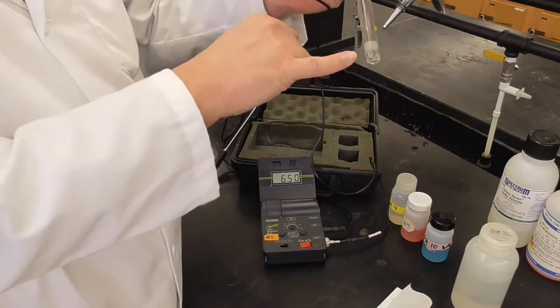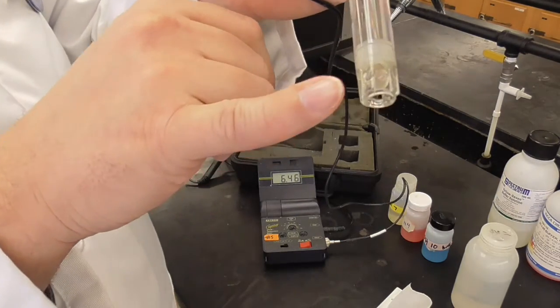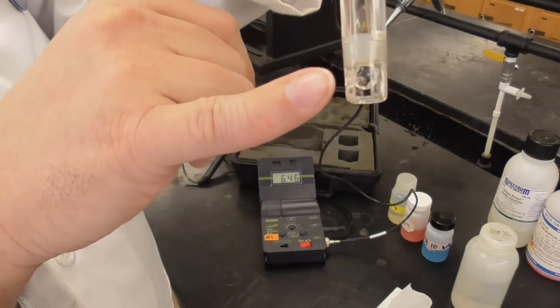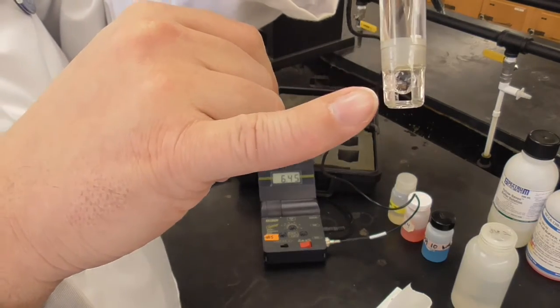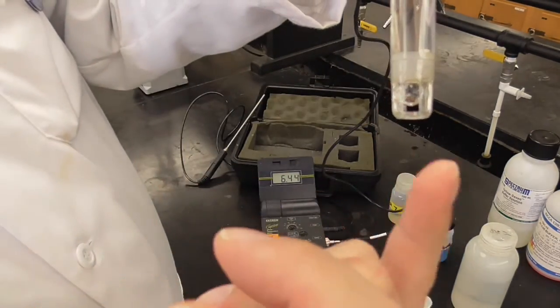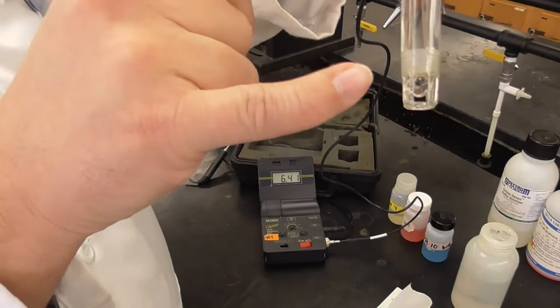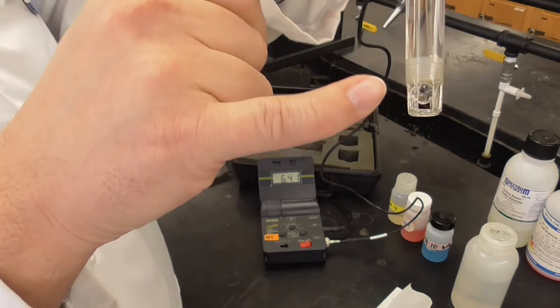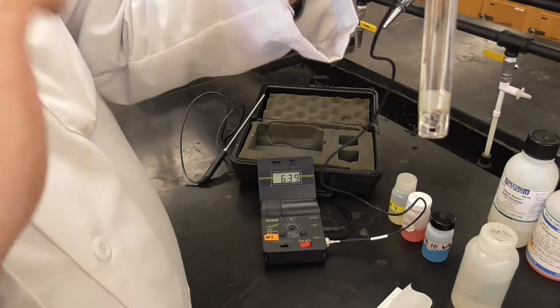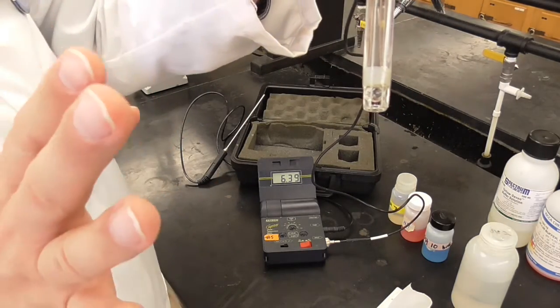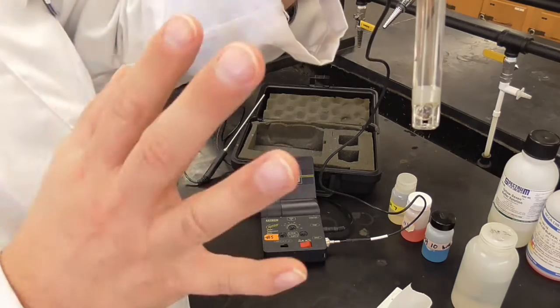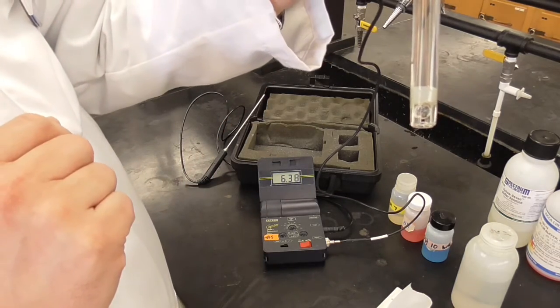All right, so here's the pH probe. The actual probe is this little ball down here at the end of this. This other piece around here is a plastic guard because that's very, very thin and fragile glass, and we don't want that to be broken. So we leave the guard on here at all times just so we don't break the pH probe. Eventually they do break with no fault of a student, but we try to protect them as much as possible.